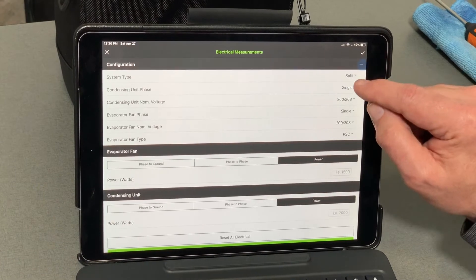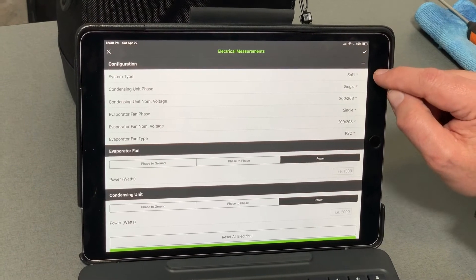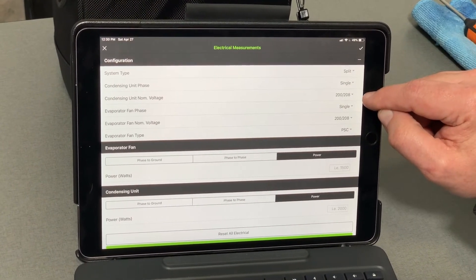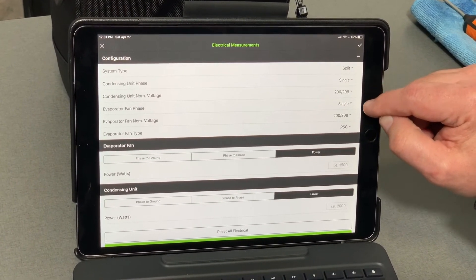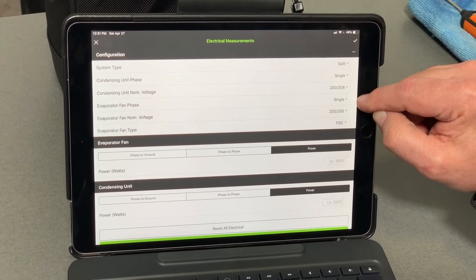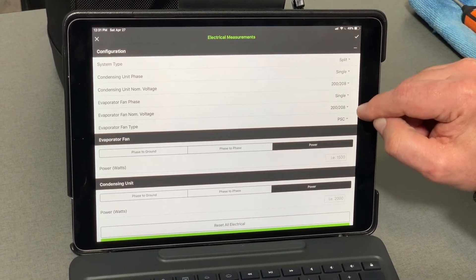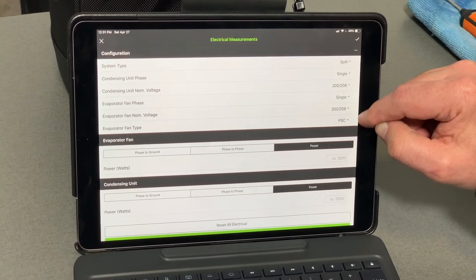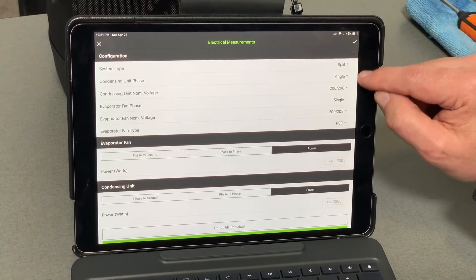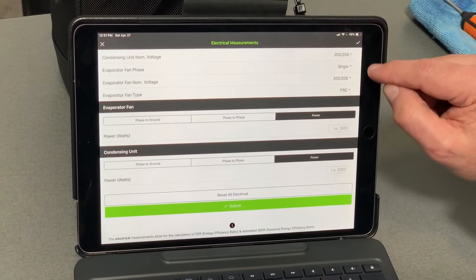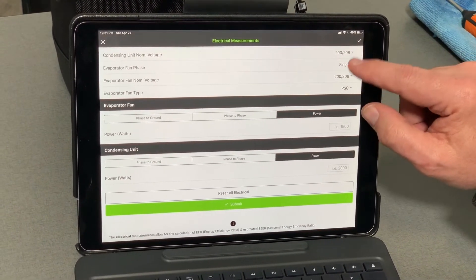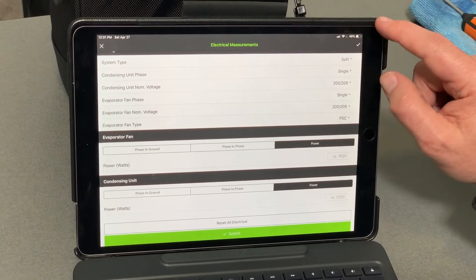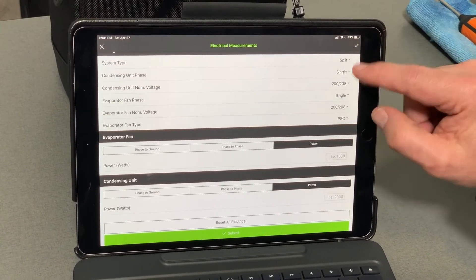Profiling is really important for electrical performance as well. If we go into electrical performance, there's also a configuration button where we tell it it's a split system, single phase, 208V condensing, single phase evaporator fan at 208V nominal, and a PSC motor. All of this is used to calculate how much power the system is using, so you need to have these entered correctly too.